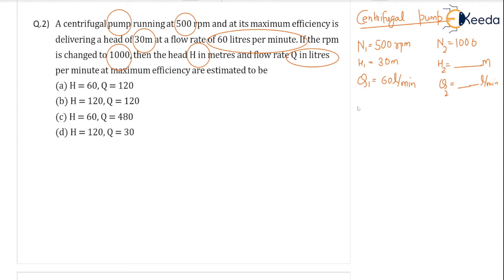So we are using the unit quantities for the ratio, N1 by root h1 equal to N2 by root h2. From this calculation, the value of h2 is coming out to be 120 meters.